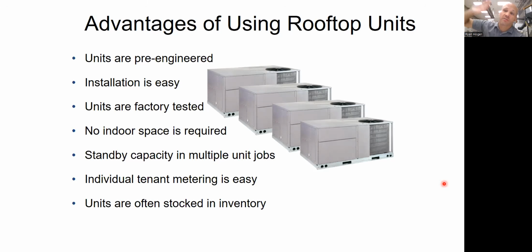And it also moves the sound from the unit more towards the outside of the building and less on the inside of the building. If you have larger areas, you can have multiple units serving that area. And if one of those goes down, you don't lose all of your capacity. For example, you might have a high school gymnasium. It might have 2 rooftops on it. If one of them goes down, you still have the other one running and you have half capacity. Or maybe it's like a big open store like a Menards or a Sam's Club or something like that.